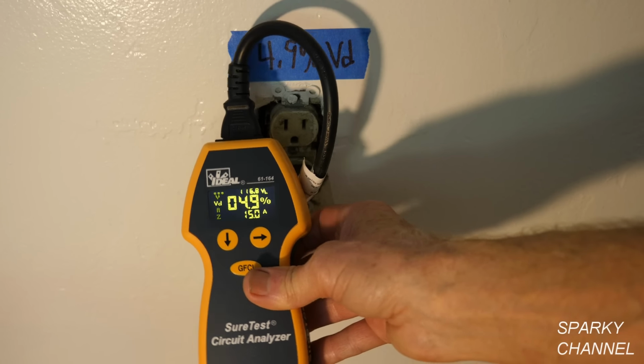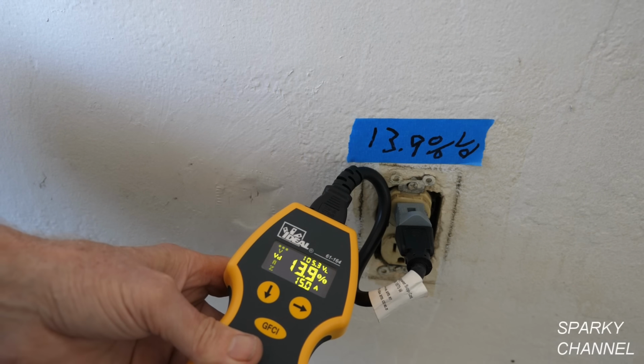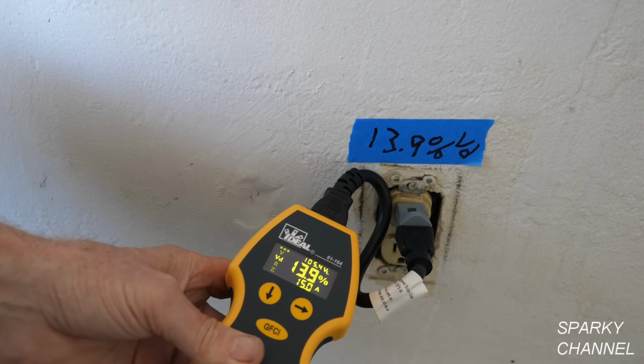This one is 8.2% voltage drop at 15 amps. So I've written that down. This one in the adjacent bedroom is 10.5% voltage drop at 15 amps. This one is 12.5%. This one is 14.5% voltage drop at 15 amps.